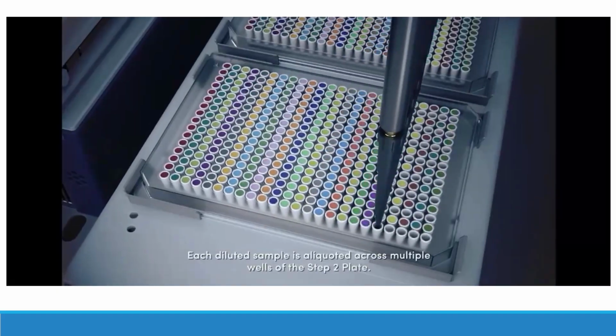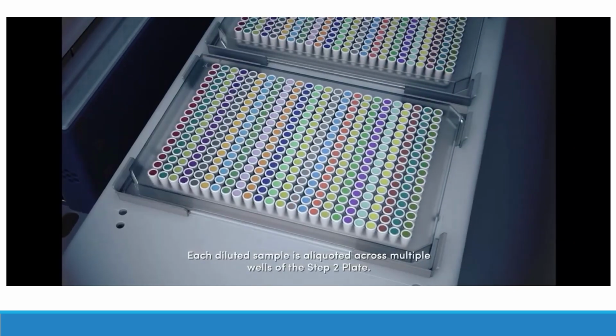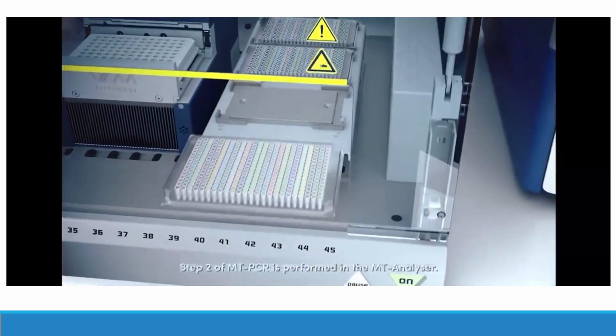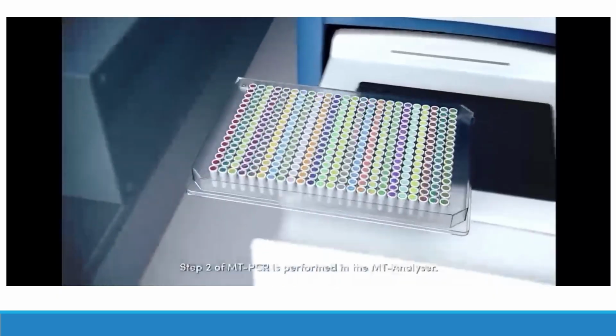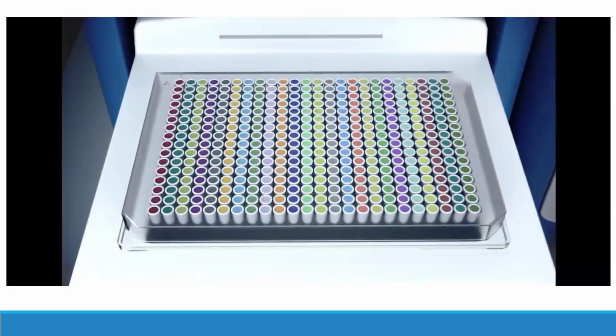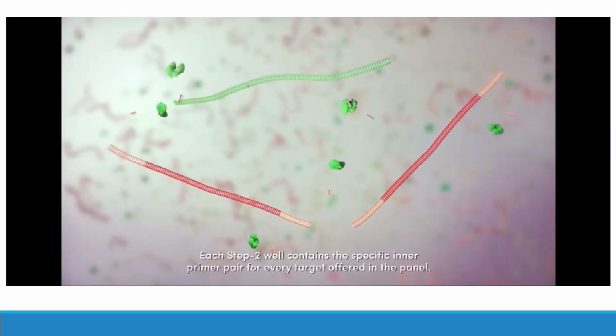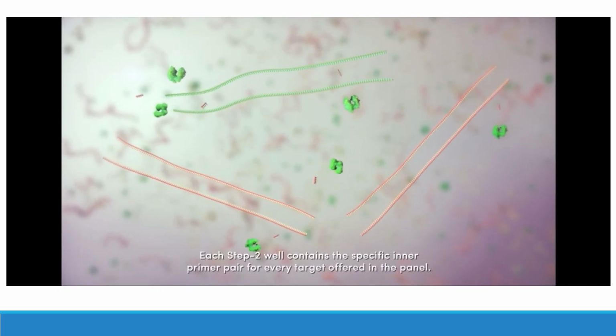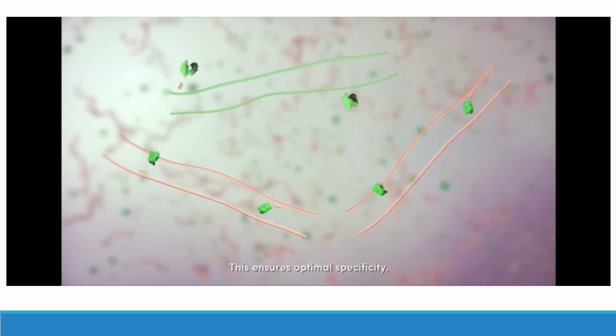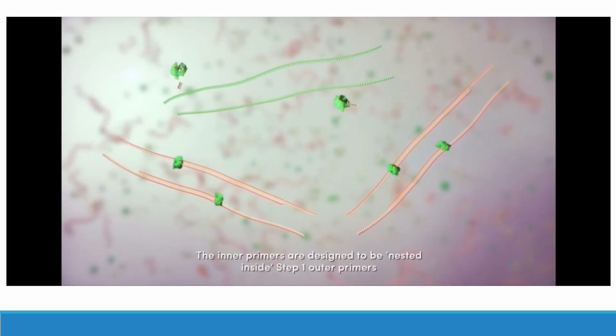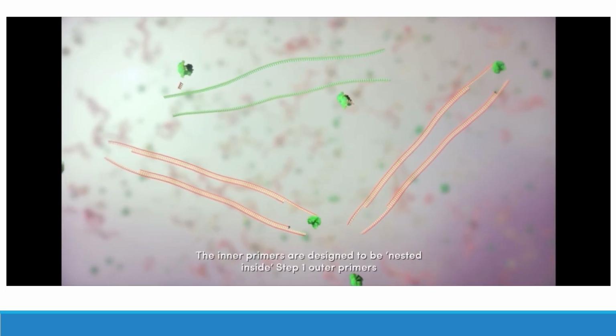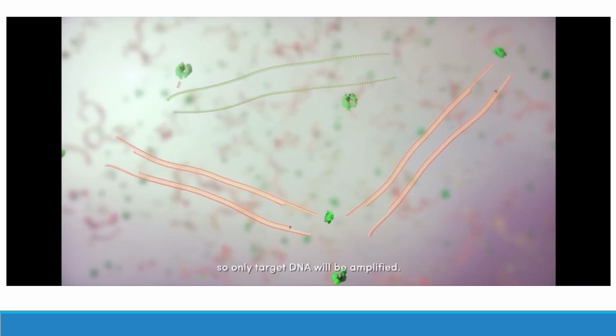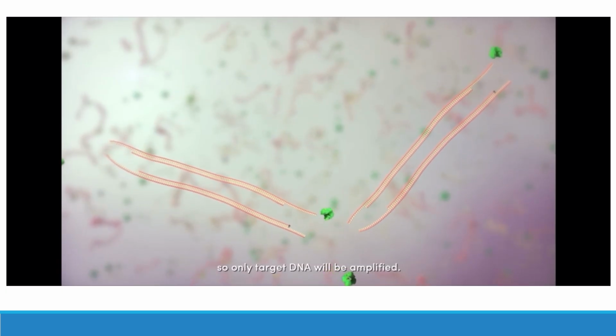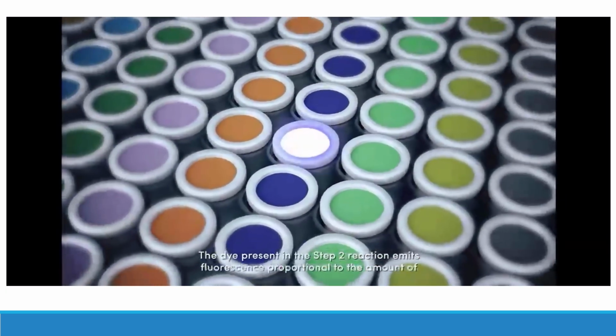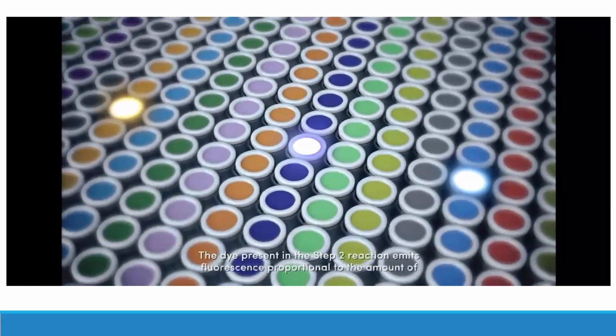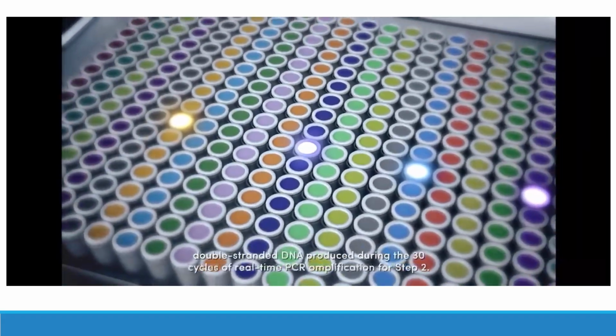Step 2 of MT-PCR is performed in the MT analyzer. Each Step 2 well contains the specific inner primer pair for every target offered in the panel. This ensures optimal specificity. The inner primers are designed to be nested inside Step 1 outer primers, so only target DNA will be amplified. The dye present in the Step 2 reaction emits fluorescence proportional to the amount of double-stranded DNA produced during the 30 cycles of real-time PCR amplification for Step 2.